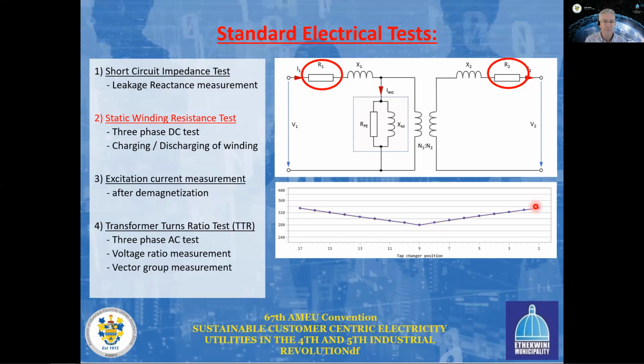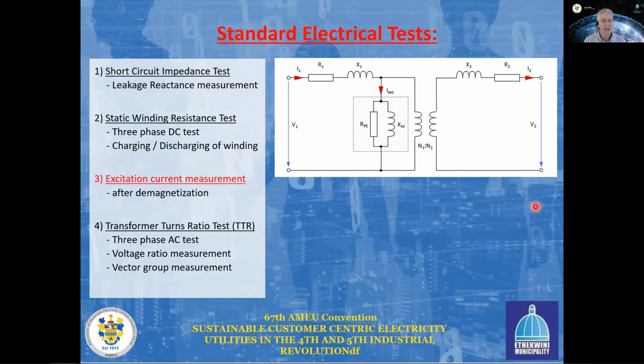Then we have the excitation current measurement that we can do on a power transformer, either at low voltage, meaning anything up to 200 volts, or at 10 kV. This typically should be done after demagnetization, particularly for the low voltage measurement, because this characterizes the core of the transformer, and it actually models the iron losses in our transformer. Here it's very important to do this after demagnetizing that core, and the test equipment can typically do this demagnetization for you as well.